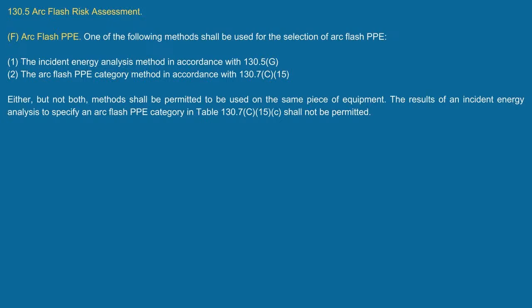Now, I will say this. When you look at 130.7 C15, there's a lot of conservative values built in there, and you can never exceed the parameters for each one of those specific pieces of equipment. And if you exceed that, then you have to do the incident energy analysis method. Okay? Gotcha. And then they put down below, you can use either, but not both methods. And I'll just leave it at that.